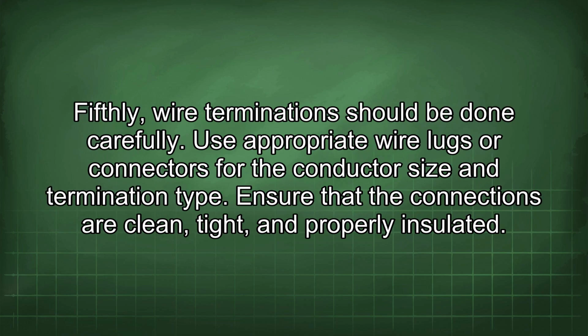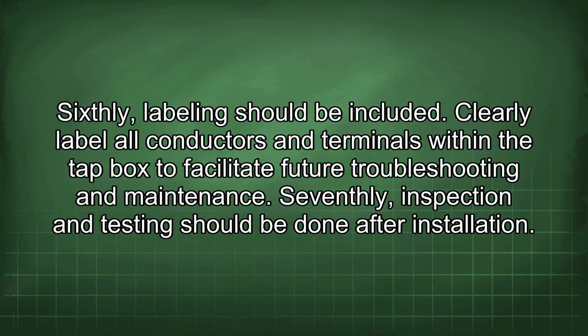Fifthly, wire termination should be done carefully. Use appropriate wire lugs or connectors for the conductor size and termination type. Ensure that the connections are clean, tight, and properly insulated. Sixthly, labeling should be included. Clearly label all conductors and terminals within the tap box to facilitate future troubleshooting and maintenance.